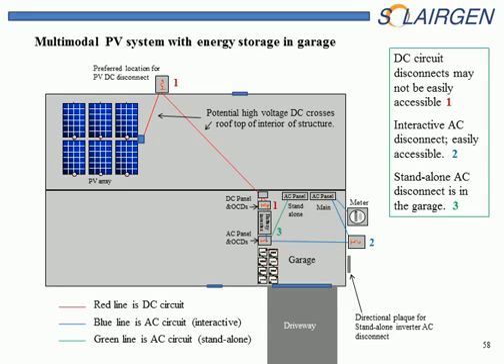Here we have another multimodal system. Now bear in mind, these multimodal systems could be standalone systems. It would be just without the number 2 blue conduits that we see there. So it would be the same, just without those. In this case, we actually have the PV array mounted on the roof. Could be the front or the back. And we have a DC disconnect on the back side of the building, and then the DC coming through. That number 1 disconnect on the back of the house may not be there. It may be inside the garage, or it could be inside the basement. So it just has to be readily accessible, as we said before.